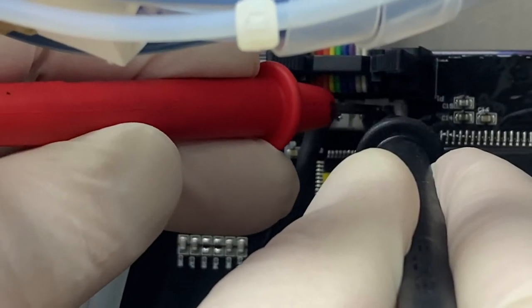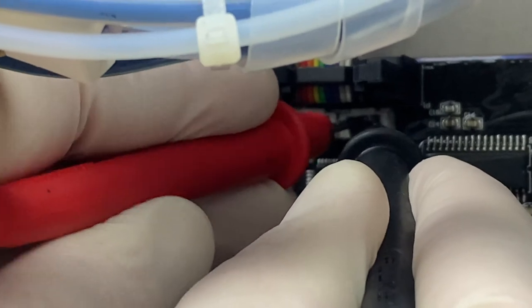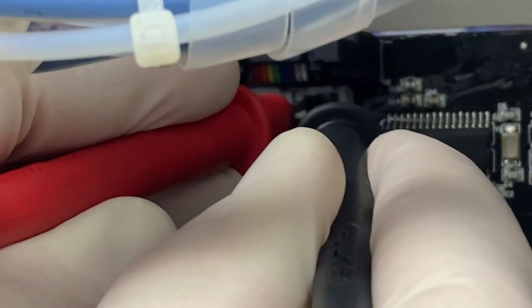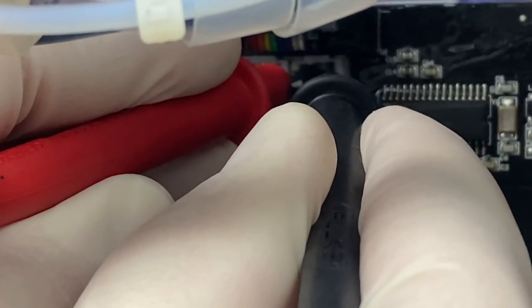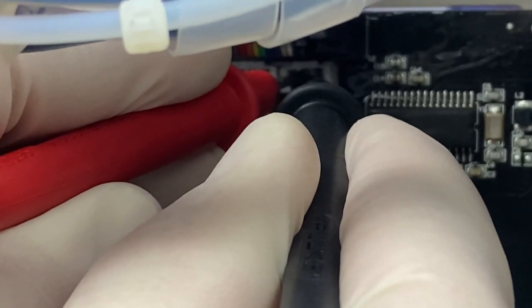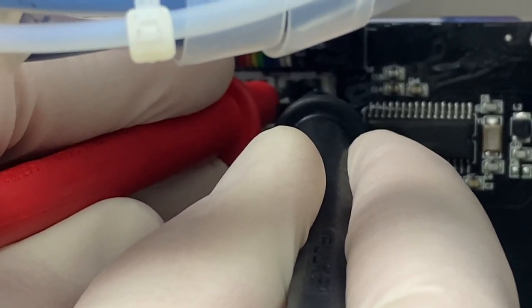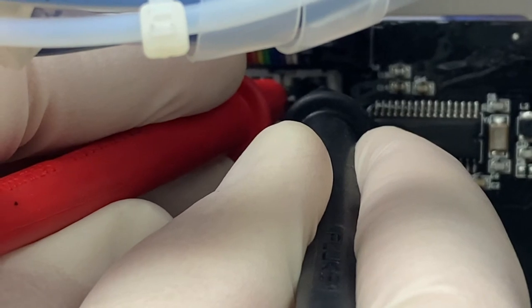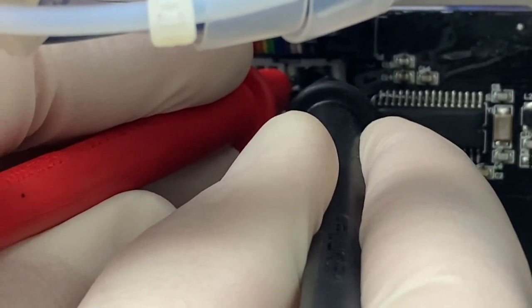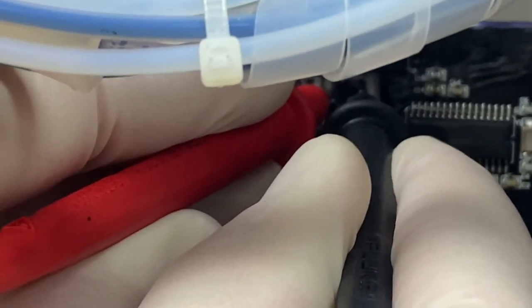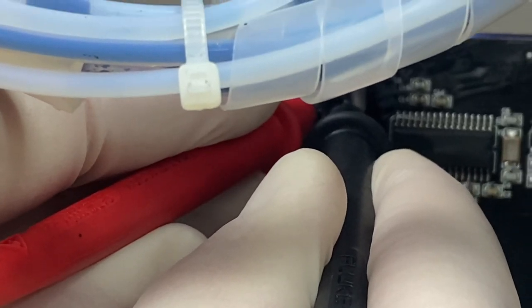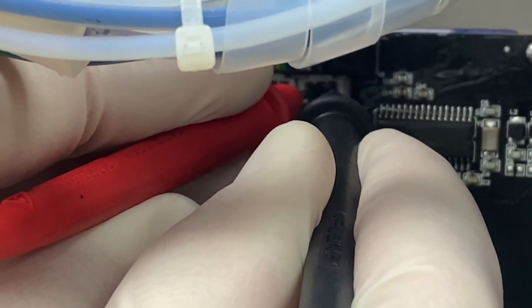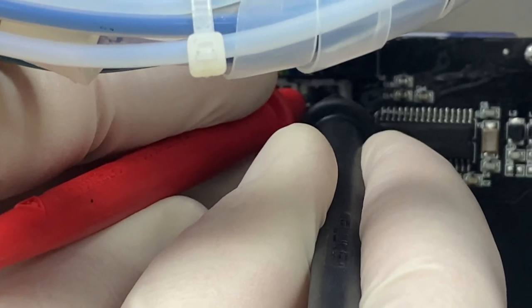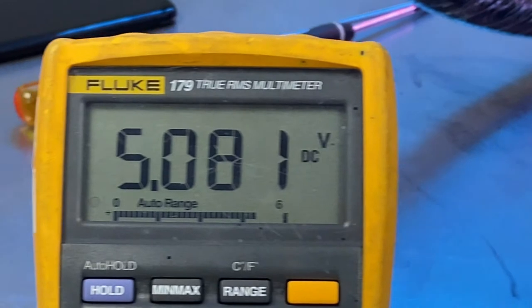The middle wire is our actual signal. If we have no cartridge present, or we have an empty cartridge, we should be seeing about 5 volts DC for a signal as well. If we install a cartridge that does have fluid, that signal should drop down to about 2 volts or a little bit lower. That's the signal the system is looking for to determine whether or not fluid is present.